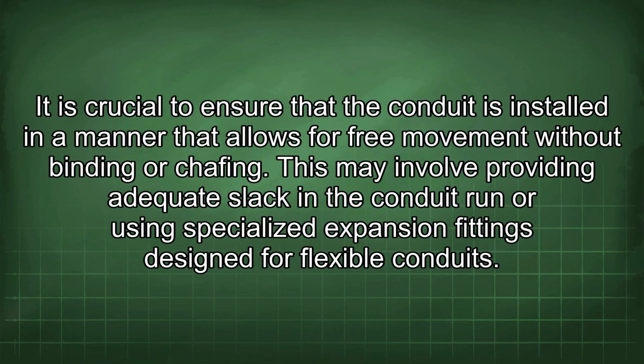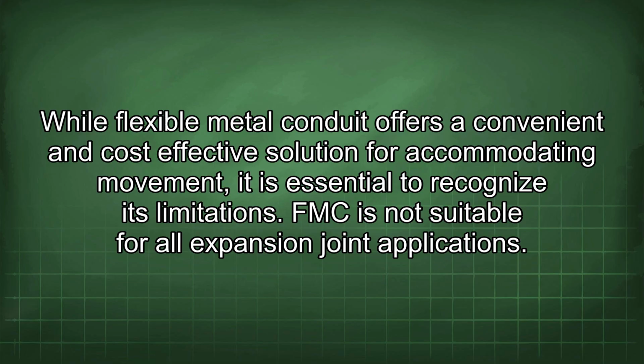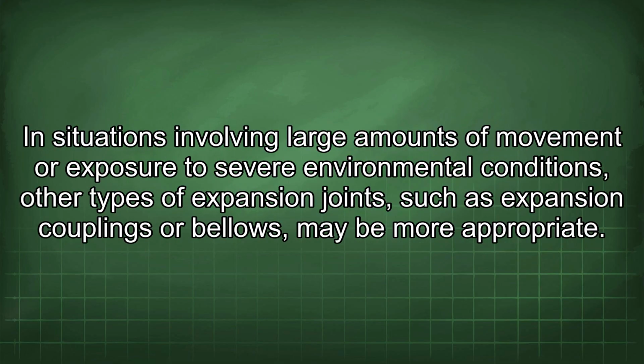It is crucial to ensure that the conduit is installed in a manner that allows for free movement without binding or chafing. This may involve providing adequate slack in the conduit run or using specialized expansion fittings designed for flexible conduits. While flexible metal conduit offers a convenient and cost-effective solution for accommodating movement, it is essential to recognize its limitations. FMC is not suitable for all expansion joint applications. In situations involving large amounts of movement or exposure to severe environmental conditions, other types of expansion joints, such as expansion couplings or bellows, may be more appropriate.